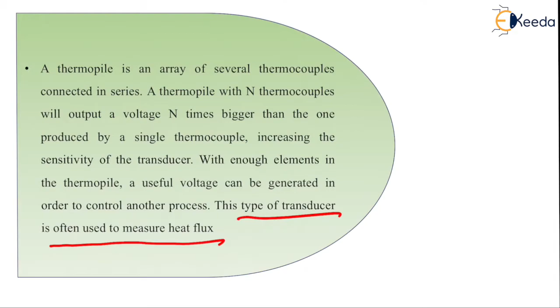This type of transducer is often used to measure heat flux, where measuring heat flux is necessary. At that point, thermopiles are used, because thermopiles are nothing but an array of thermocouples, where the summation of all the voltages at the junctions is calculated, and that summation is the output voltage, which is proportional to the temperature differences at the two terminals.